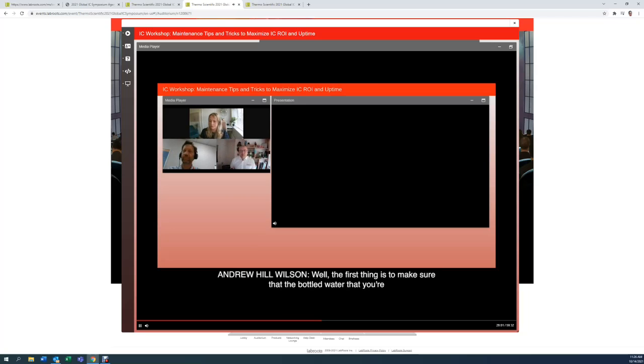Well, the first thing is to make sure that the bottled water that you're purchasing actually has a specification on the side of it, so at least at some point in its life, it was 18.2 megohm water. That's the first thing. There are certain chemistries that will cope with it better than other chemistries. For instance, the carbonate chemistry is quite a robust chemistry, and that possibly will cope with it better than, let's say, a hydroxide chemistry. You will see, or possibly will see, an increased background conductivity. You might see some extra peaks kicking around in there as well.